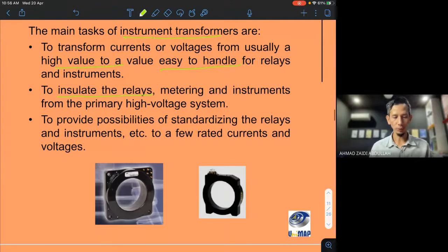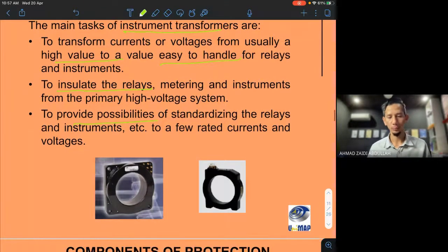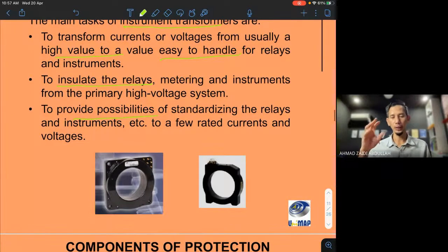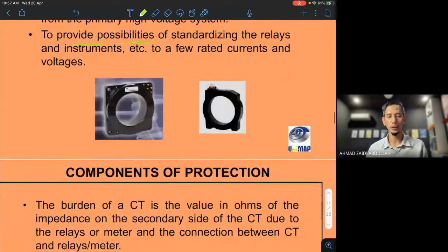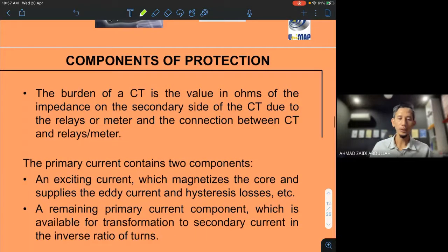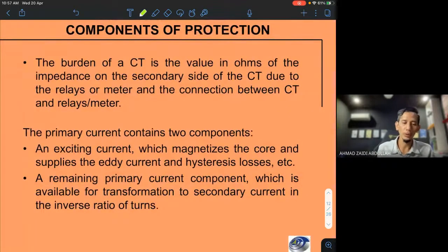Okay, and then to provide the possibility of standardizing the relay and instrument, because the relay, or instrument metering lah, has a standard value. So that's why we need to have this CT, to make sure that the relay can function lah. Okay. And then under CT, we have a burden.